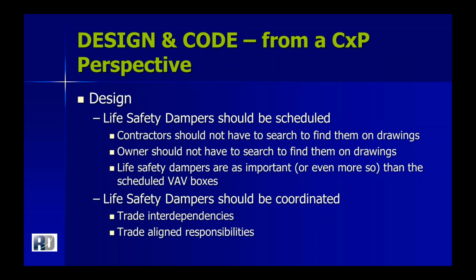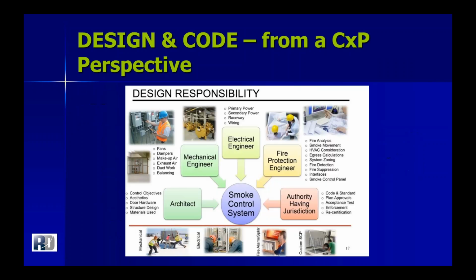And this moves right into these should be coordinated. So obviously if they're scheduled, it makes the coordination process easier as well. There are numerous trade interdependencies and trade-aligned responsibilities that come with these life safety dampers. The engineer has a large job to wrap their arms around the process and the people that are involved in the utilization of these dampers. They touch the architect, the mechanical engineer, the fire alarm contractor, the electrical contractor, the AHJ, the CX, and so many folks, and so many people have a small responsibility or a large responsibility depending on the outcome of that particular project. So it's really important to get your arms wrapped around that early in the process, and it makes everything go smoother in the end.